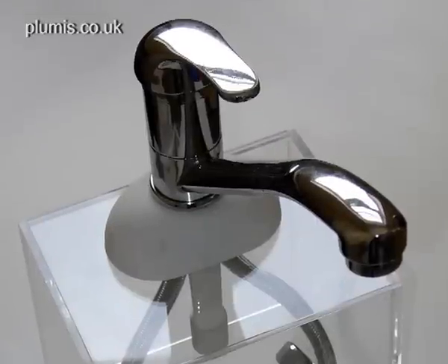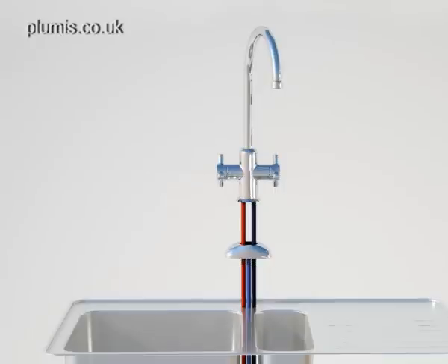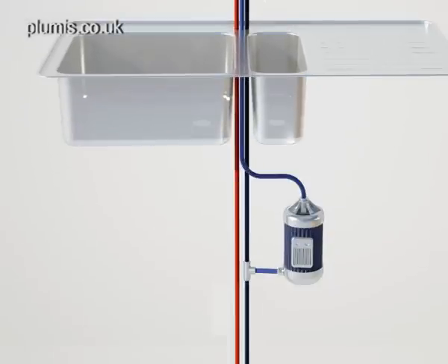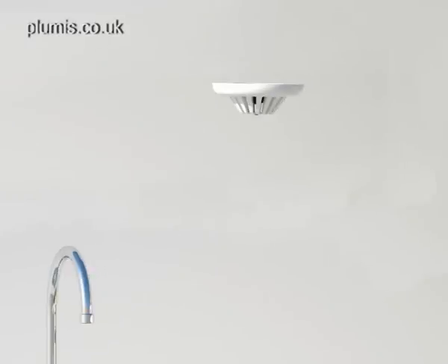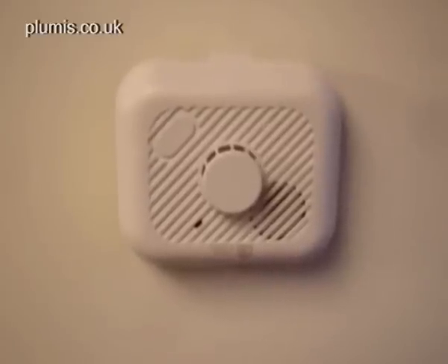Let's have a closer look at AutoMist. Multiple mist nozzles mount discreetly under the tap and are plumbed into ordinary mains water. Mist requires high pressure though — this is provided by a compact pump which is fitted under the sink. The system is activated by a smart fire sensor that won't be fooled by everyday kitchen events like burning the toast.